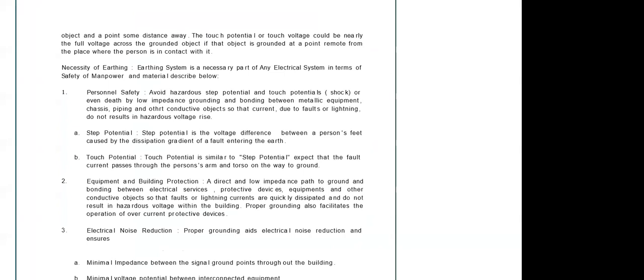So as I discussed initially, the necessity of earthing is personal safety. This is most important. If any electrical fault is happening, we need to find a route through which the fault current flows to the earth without hampering any system or personal safety. We need to avoid this hazardous step potential and touch potential, commonly known as shock, or even death, by low impedance grounding and bonding between metallic equipment. This I will explain when we come to the lightning protection system, how dangerous it is. Piping and other conductive objects are bonded so that current due to faults or lightning does not result in a hazardous voltage rise.